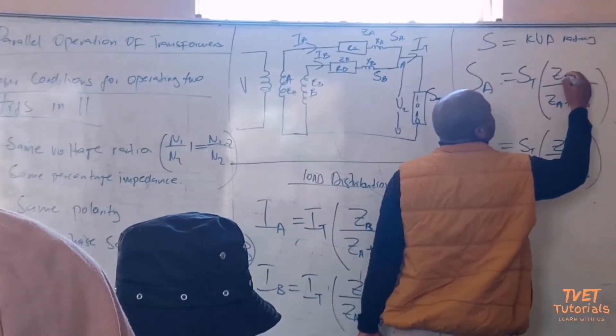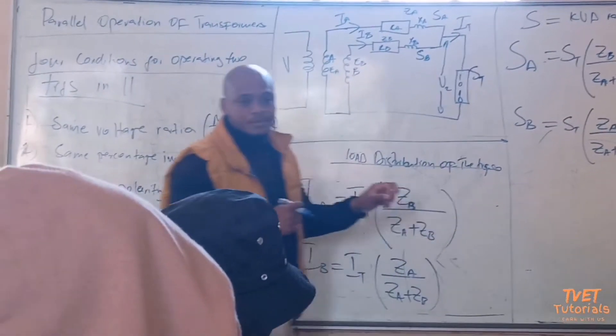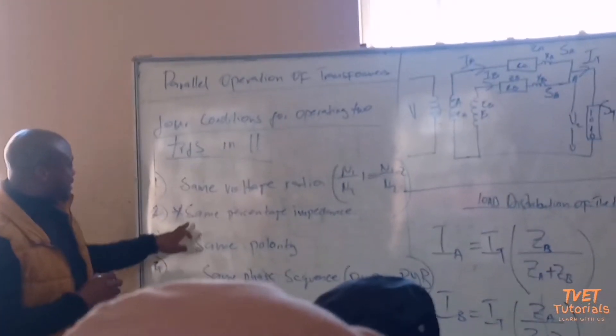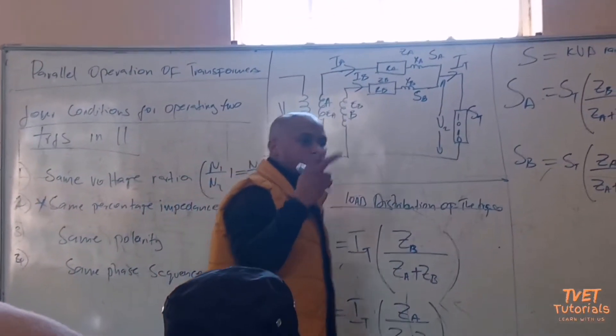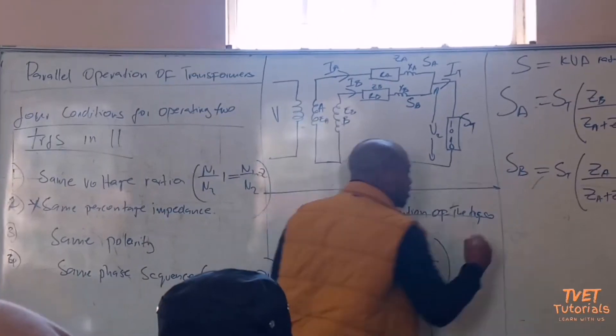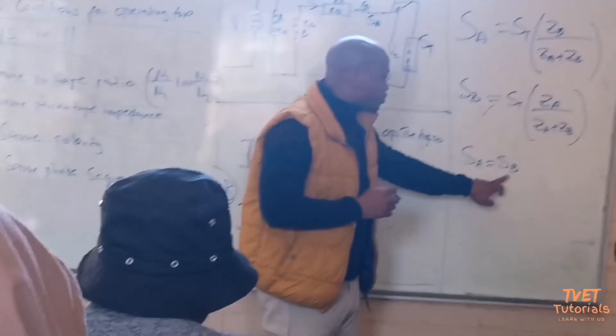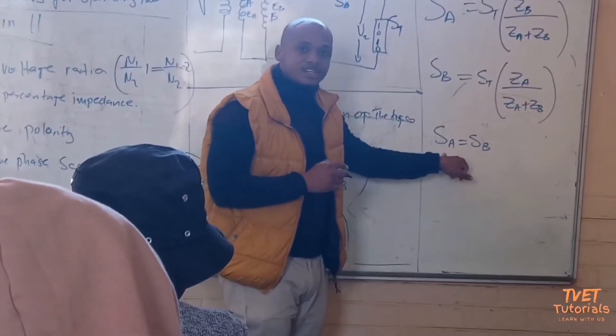If you are looking for A, use ZB at the numerator; if looking for B, use ZA at the numerator — you just swap them. The main condition for our calculations is percentage impedance. If SA is equal to SB, you will use these equations as they are.